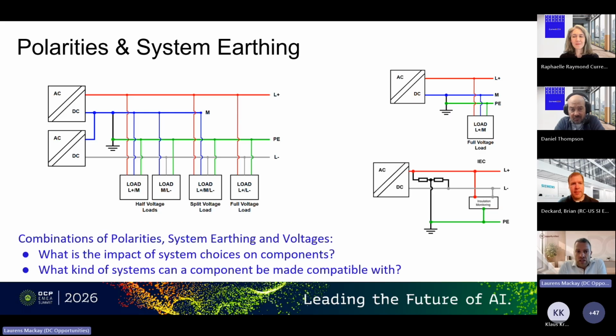Then for these different systems, here are a couple of examples of how they can be grounded or earthed. Here on the left-hand side, you see a bipolar system with a partially distributed midpoint conductor that is TN-S grounded. In North America, that's called solidly grounded. You see the grounding point where the protective earth is connected with the M conductor. In this case, it's supplied with two isolated converters from an AC grid, as drawn here.